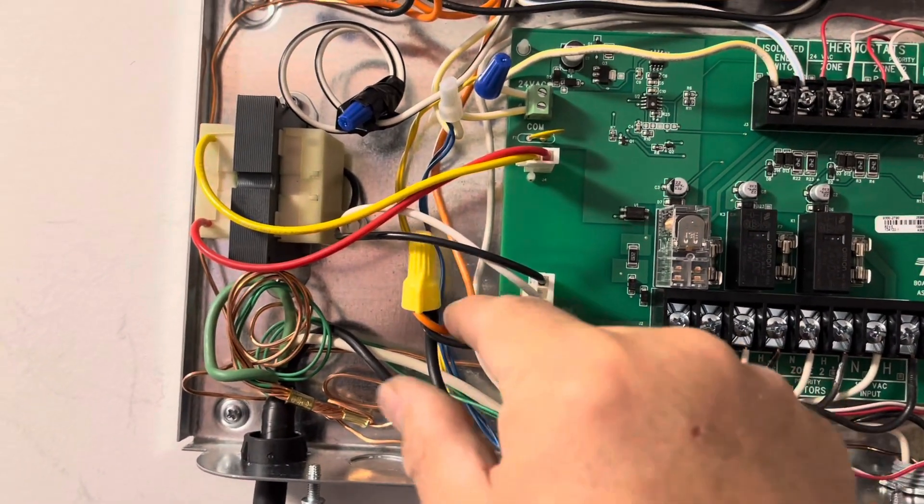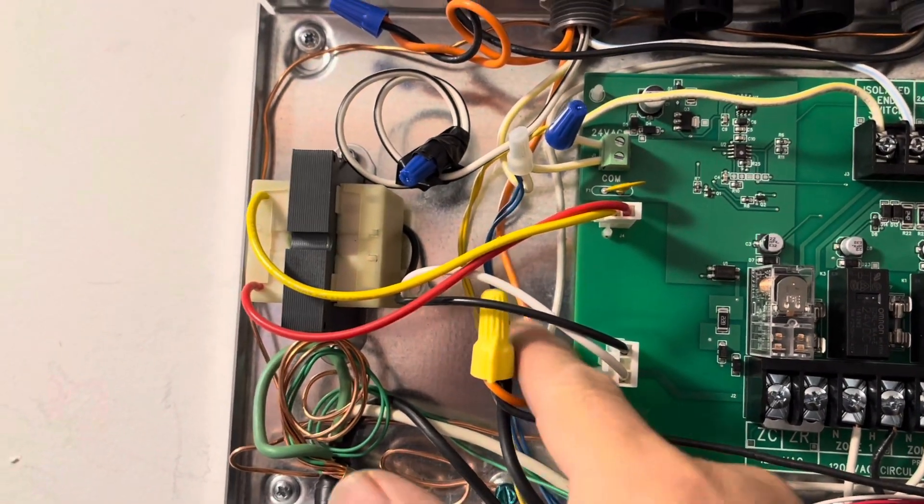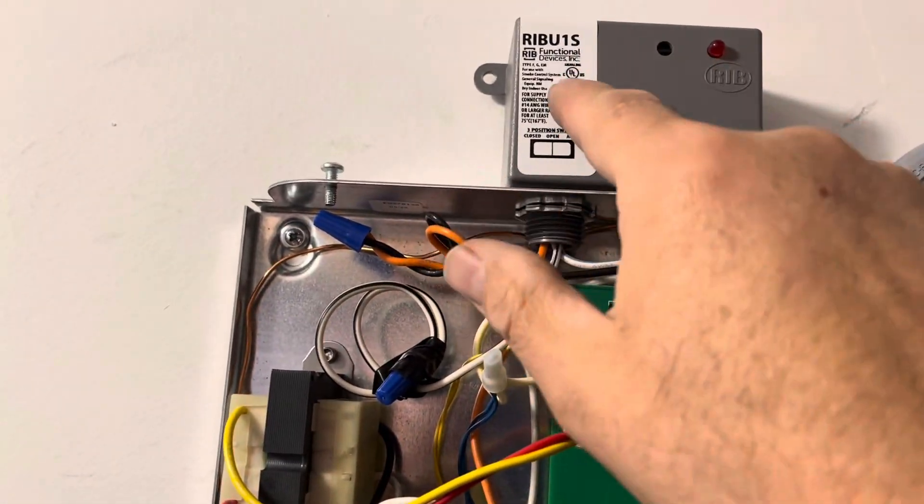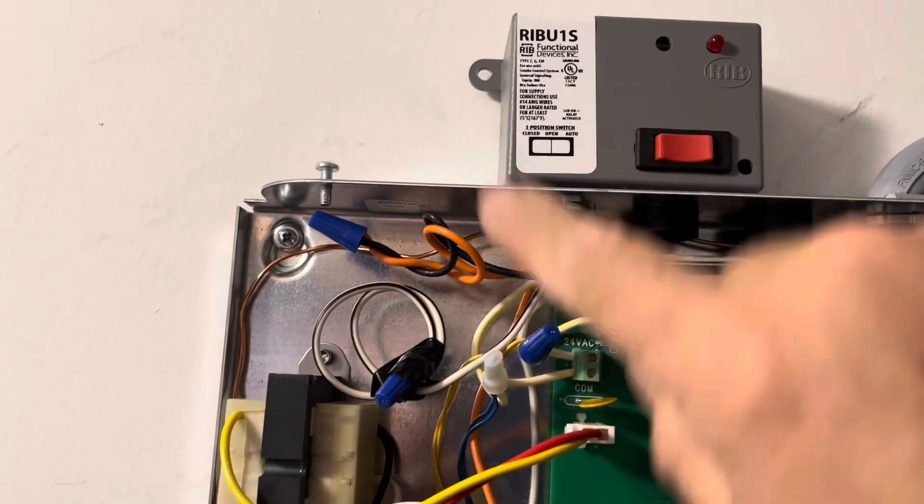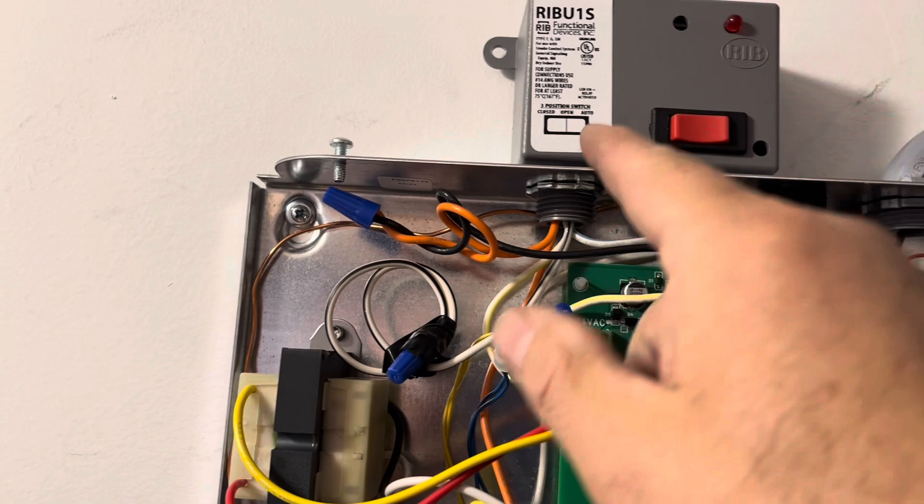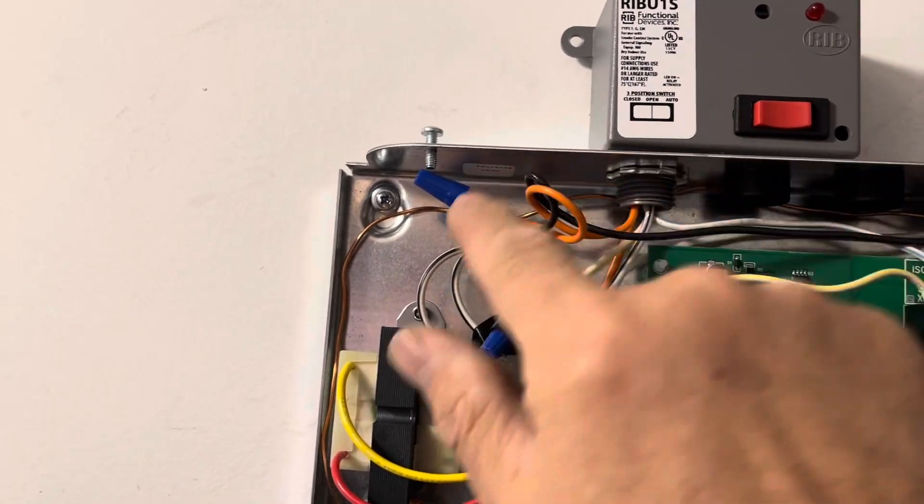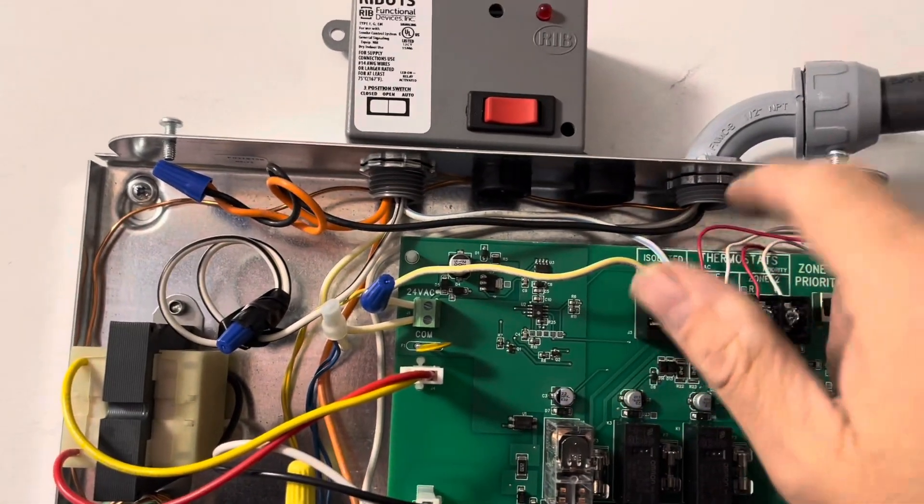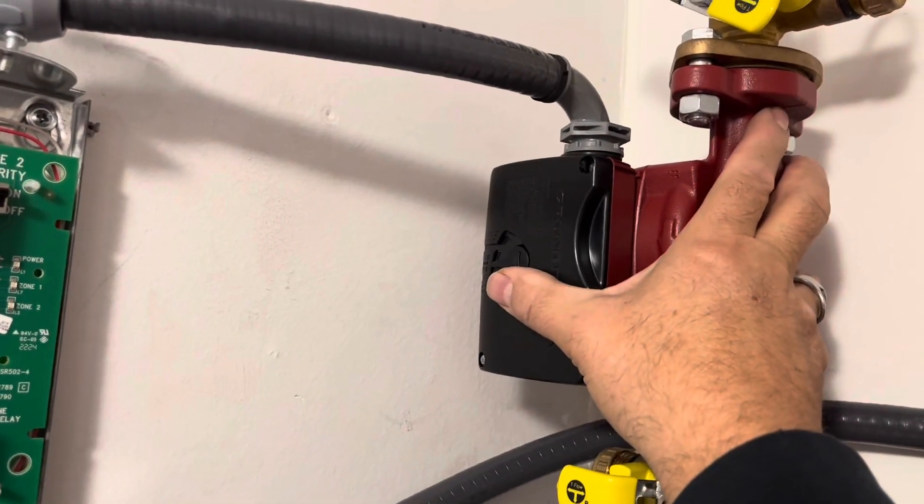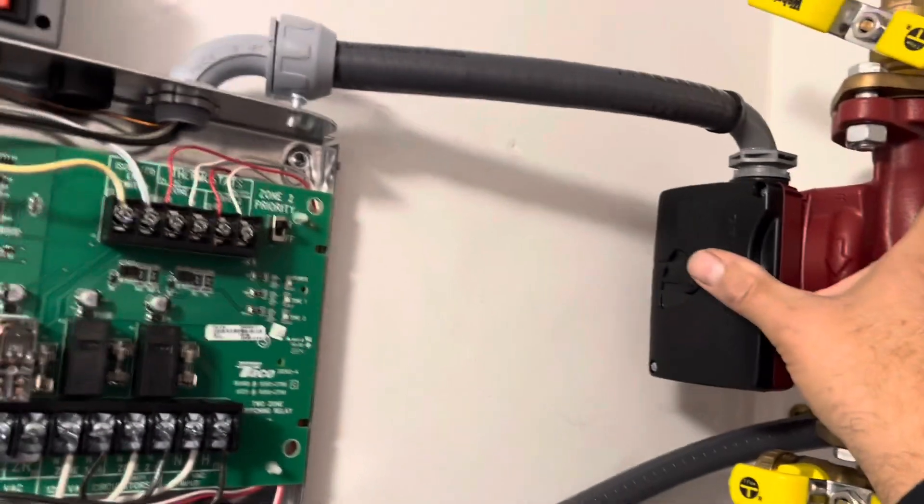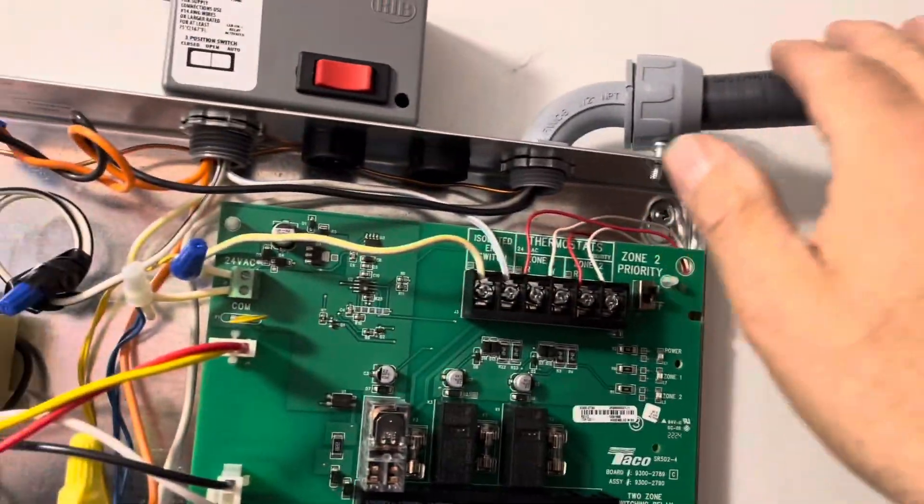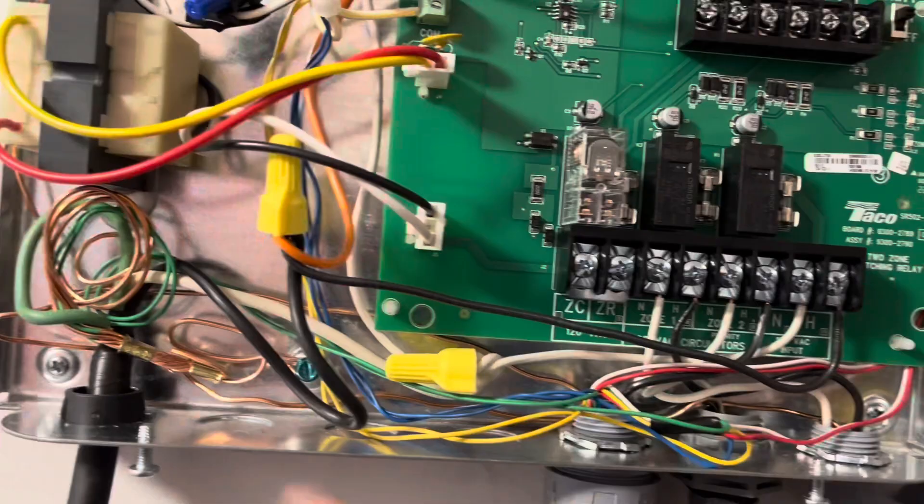This hot and this neutral are branched, so part of the hot branches off and goes up into this coil. This is a relay in a box and it'll be switched. When that switch activates and turns on, the power will come out here on this one, connect on this line, go up through here and feed the primary circuit motor pump. And then neutral comes back of course and connects back into here.